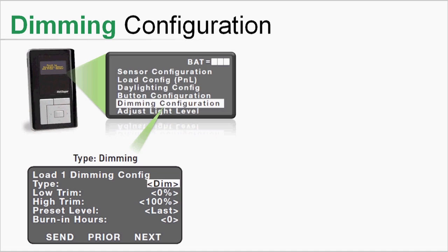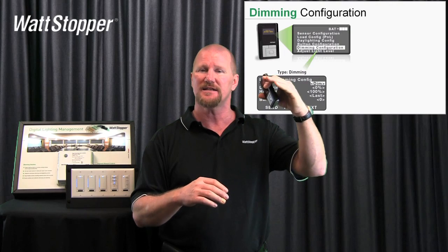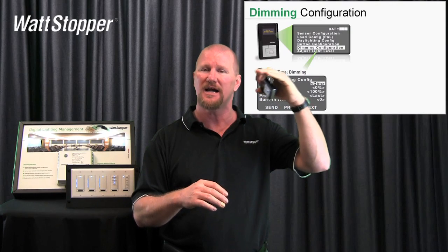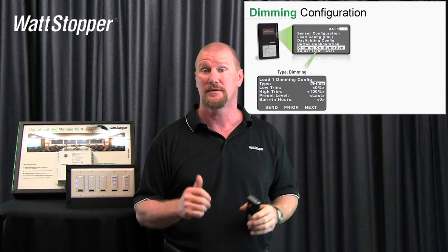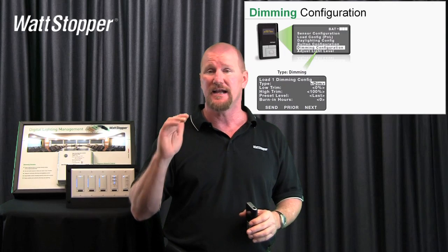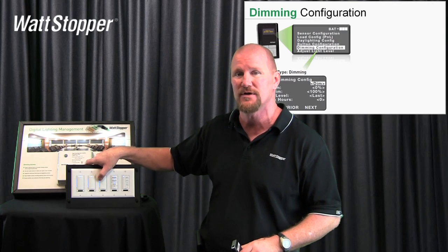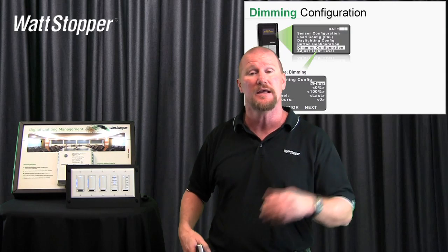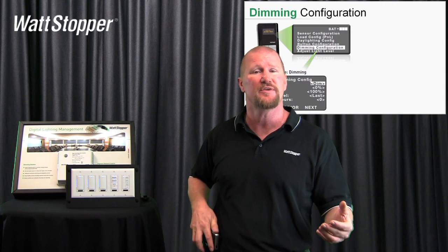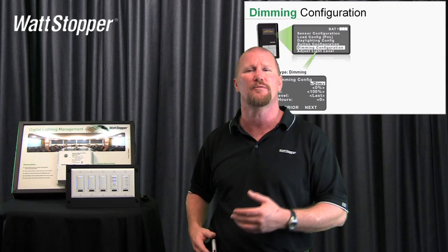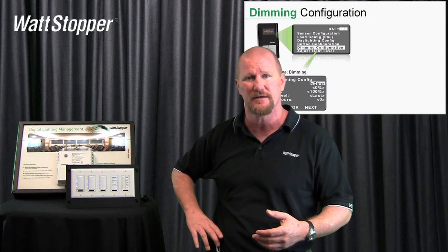So what can we change in dimming configuration? You can see here we can change low trim and high trim — these are hard limits. If I set a high trim, this is the highest level the system will allow. If you set it at 80%, you get 80%. I don't care how long you press and hold this dimmer, you're going to be capped at 80%. It's a powerful feature, but it can also be a feature I would exercise caution when using.